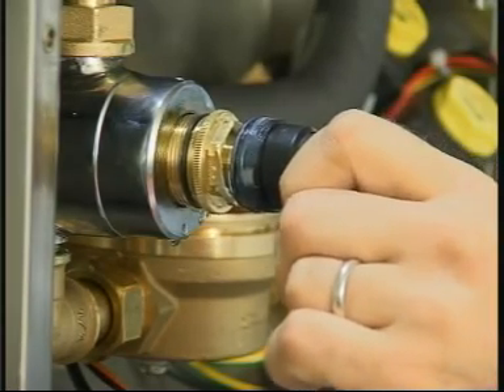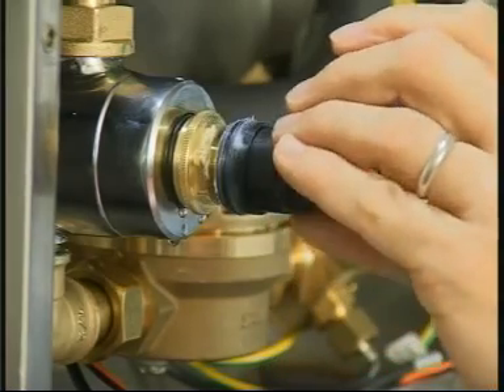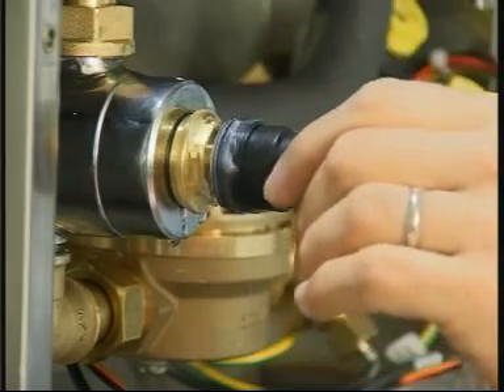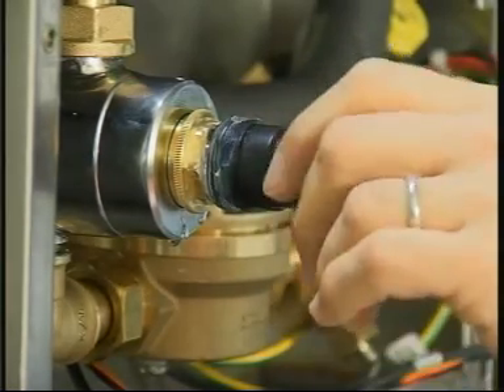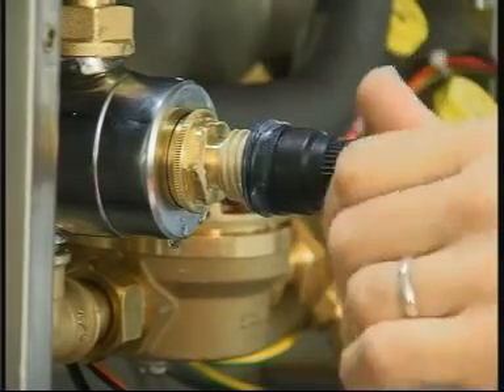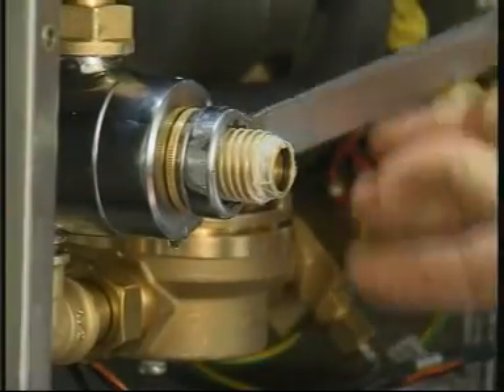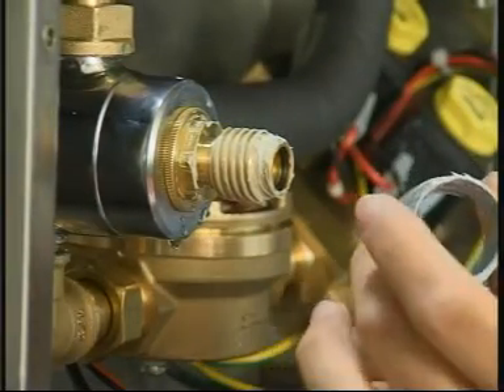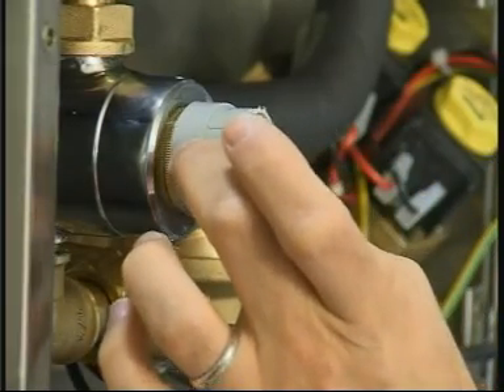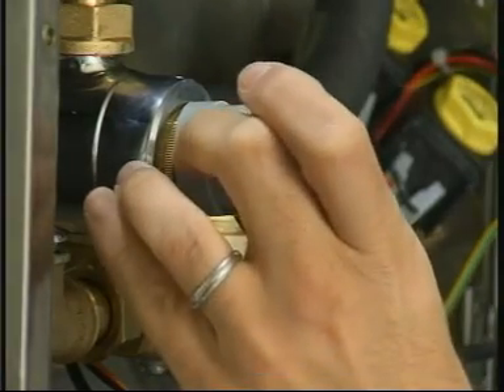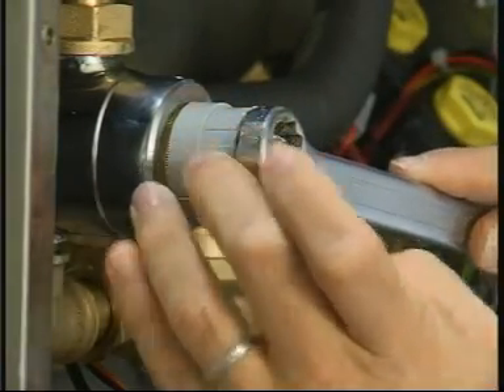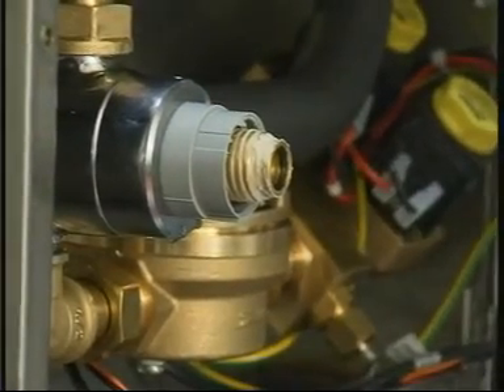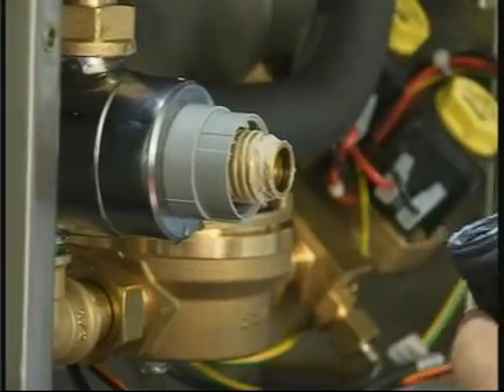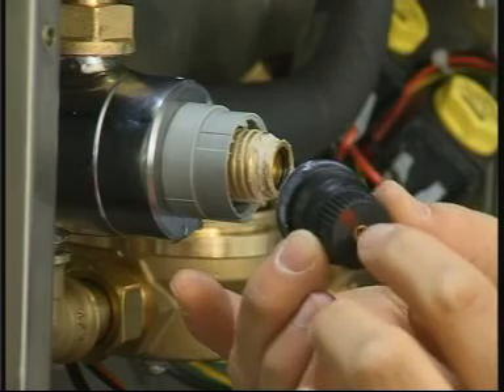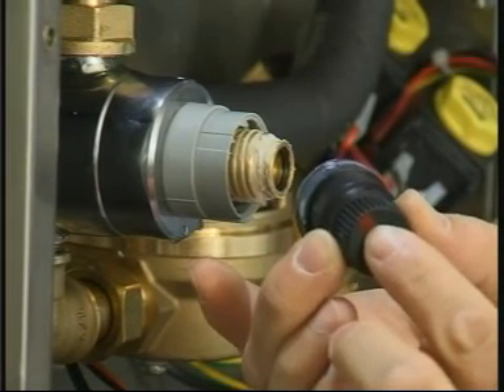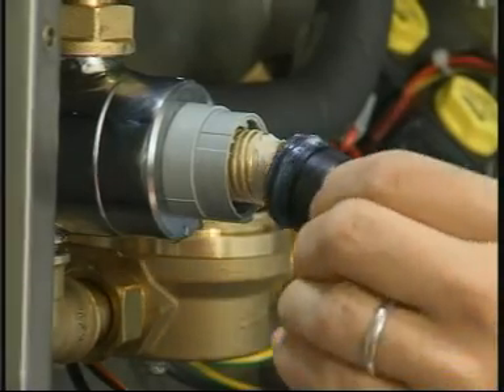To reassemble the thermostatic element, screw clockwise the element into the casing using the black knob extension lead until the screwing is nearly complete, but without using too much force. Unscrew the black knob pin and tighten the thermostatic element with the spanner. Assemble the grey plastic ring, taking great care to place the indicator in relief in the image at 6 o'clock. That is to say, facing down at the centre. Screw the black knob pin on its seat, taking great care that the red indicator is at 12 o'clock position.